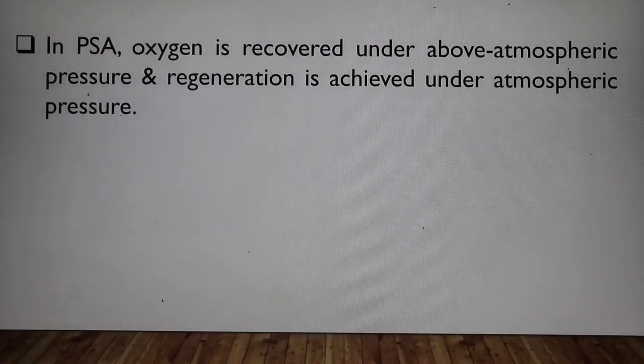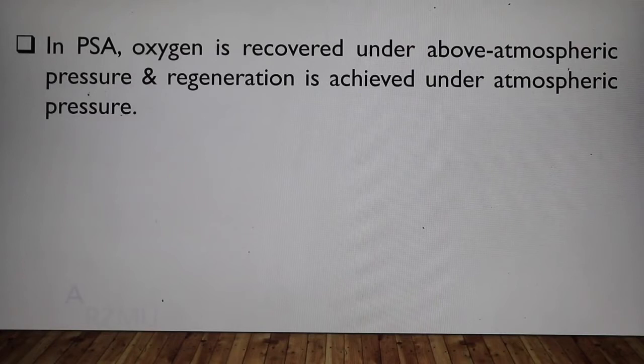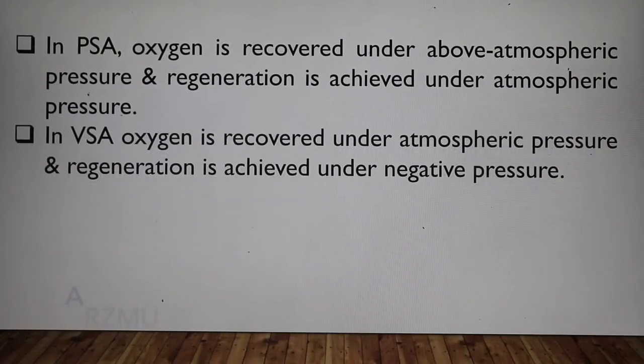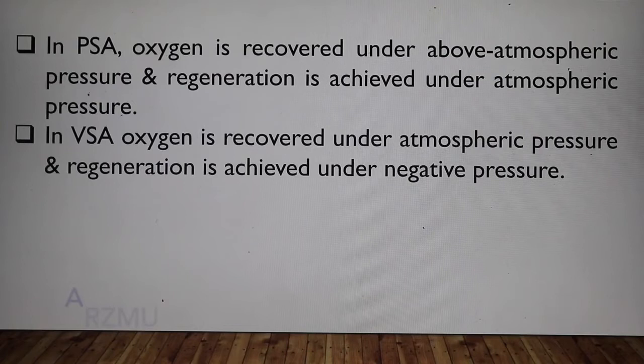In pressure swing adsorption, oxygen is recovered under above atmospheric pressure and regeneration is achieved under atmospheric pressure. In vacuum swing adsorption, oxygen is recovered under atmospheric pressure and regeneration is achieved under negative pressure. The mixed systems combine pressure variations from positive to negative.